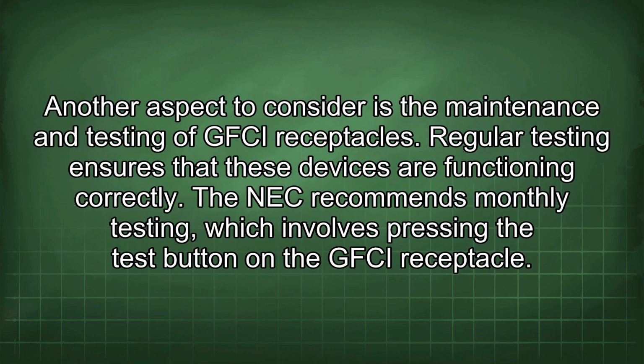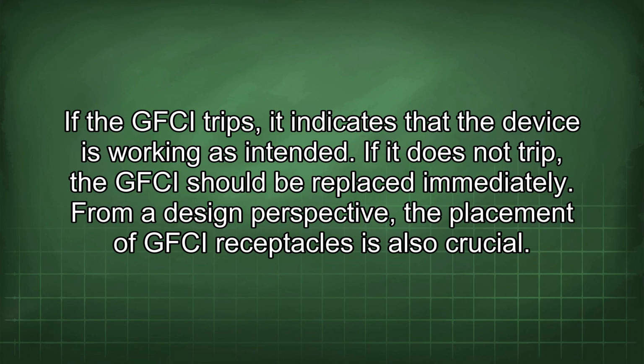Another aspect to consider is the maintenance and testing of GFCI receptacles. Regular testing ensures that these devices are functioning correctly. The NEC recommends monthly testing, which involves pressing the test button on the GFCI receptacle. If the GFCI trips, it indicates that the device is working as intended. If it does not trip, the GFCI should be replaced immediately.